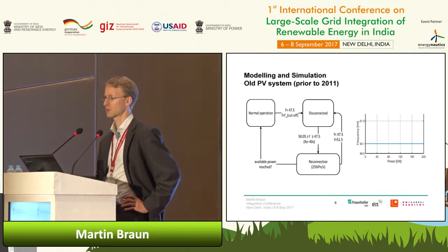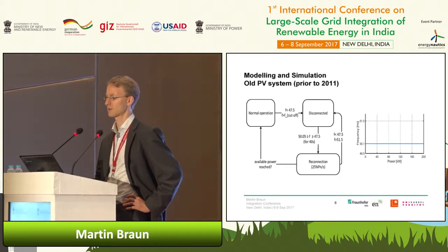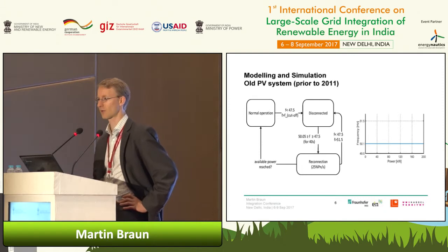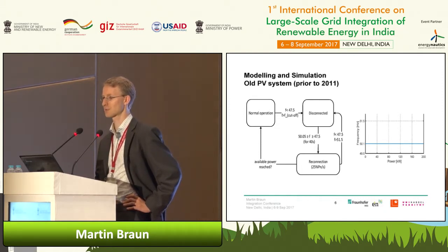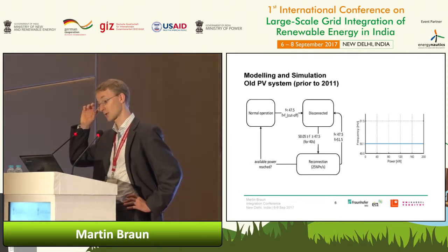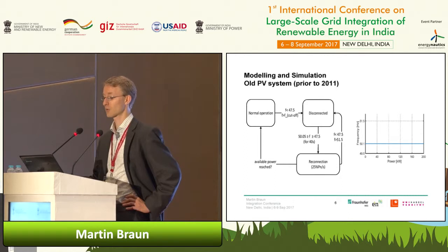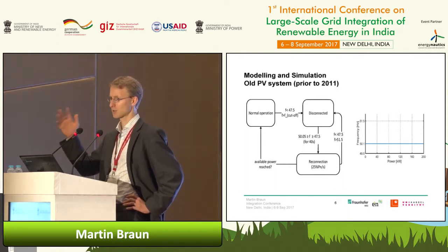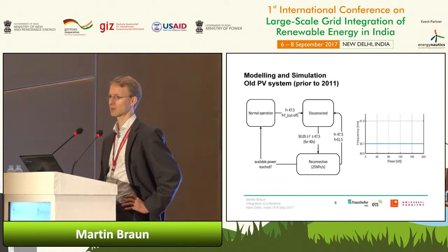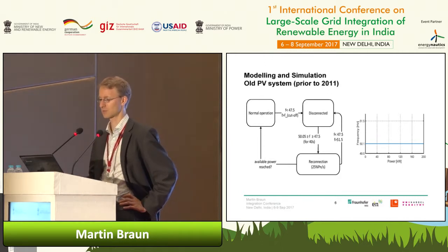Maybe you can remember, 2 days ago we already discussed in the plenary panel the 50.2 Hertz problem. It was a time when hundreds of thousands of PV plants had over frequency protection at 50.2 Hertz, and within 200 milliseconds, many gigawatts could have been disconnected. And during the retrofitting, there was one category of hundreds of thousands of plants that were not able to implement this dynamic reduction.